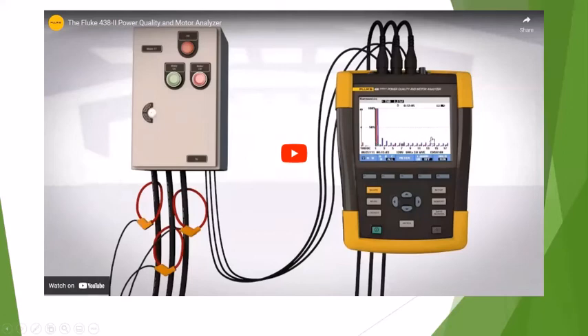But I recommend that you put a metering in. I know when I did a bunch of work for Sterilite Corporation, they had originally a lot of inductive load. Then a lot of machines were converted over to AC inverters to help get their power factor back in line, plus get the motors all running more efficiently. But what we did first, we took a snapshot of where we were on each 2000 amp service and took an evaluation of what the harmonics really were, because one machine can also help cancel the others. We've actually found the result to be quite a bit lower than what you can pencil out on paper. So I do recommend you get a snapshot on your 480 volt side, or 400 volt, or 380, whatever you're doing. Get it on the low voltage side, which is on your side, and determine what those spectrums look like.